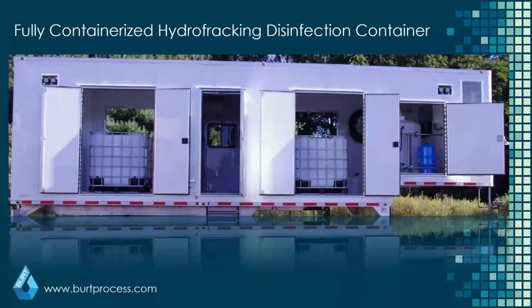We have a couple of pictures later on in the presentation which show a number of different custom lift stations that are on carts. One of the issues of anything that's mobile, whether it's DOT or something that's going to be pushed around your facility, is thinking about things like venting. If you have specialized venting, you need the ability to vent it wherever you end up moving the system. You need to have the right power to it, which is not going to be a hard powered connection. These are the kinds of things that, on the design end, you end up looking at when you move into the realm of custom systems.